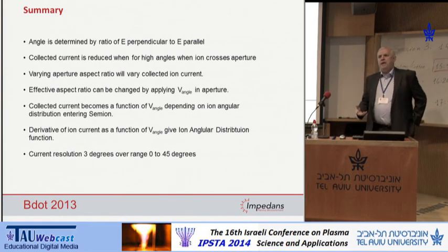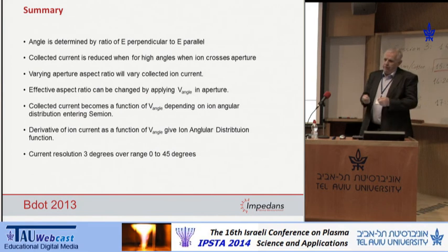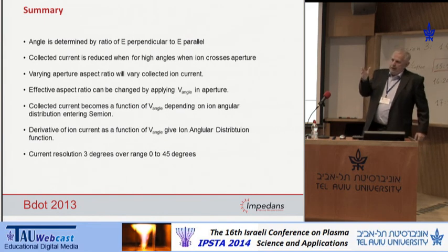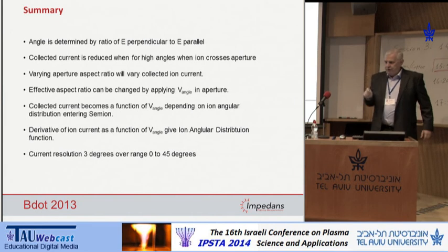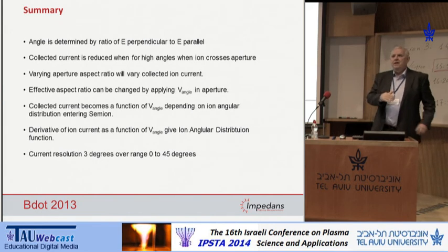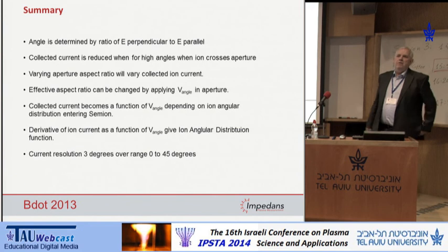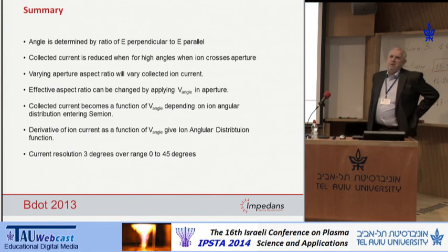We have looked for scattering on the grids, and we've looked at aligning the grids and randomizing the grids. If we align the grids, we see some structure, and we think it's due to interference because of scattering. If we randomize the grids, we see no effect. A typical ion trajectory does not go through the same hole, it goes through a different hole on the grid. So by randomizing the grids, you remove any effects. That's what we've found by experience.